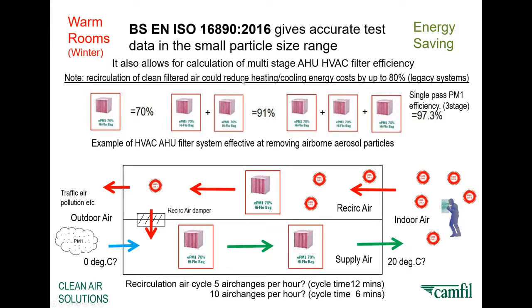You would actually possibly save huge amounts of energy in terms of having to heat air, because if you have 100% fresh air, or outside air, I would say, coming into the building, you have to heat that, and it's an incredibly high heating load, incredibly high energy use. We need to be finding ways of reducing that energy consumption.